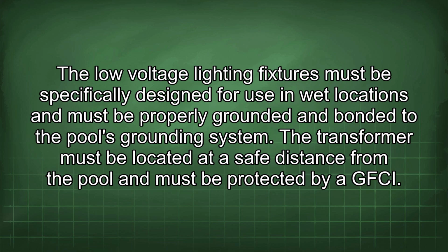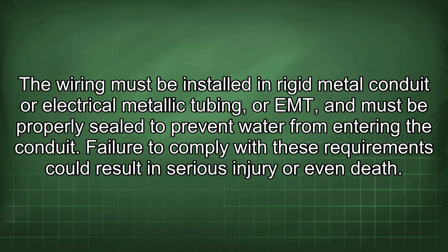The transformer must be located at a safe distance from the pool and must be protected by a GFCI. The wiring must be installed in rigid metal conduit or electrical metallic tubing, or EMT, and must be properly sealed to prevent water from entering the conduit. Failure to comply with these requirements could result in serious injury or even death.